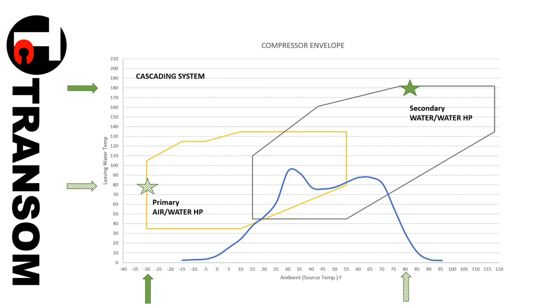That's very true. What you're saying is that we would have this on a very cold day, but then you could slide down to about 180, 170, 160, and so on, to not have to work it as hard. As you go down, if you remember the start, those pressure ratios are going down, so the compressor is doing less work, and your COP is better. Because we're at the outer edges of it, it's almost exponential, not quite, in that you're working hard for it. You can do it, but it's a lot of work. So if you can step in a little bit, it really makes a big difference.